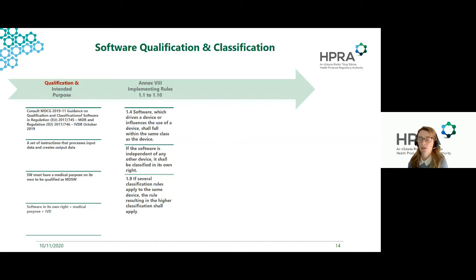Then, according to the second indent of rule 1.4, if the software is independent of any other device, it shall be classified in its own right. In determining the proper classification of medical device software under the IVDR, the manufacturer shall consider all classification and implementing rules of the IVDR. And again, as spelled out by implementing rule 1.1 of Annex 8 of the IVDR, the application of the classification rules shall be governed by the intended purpose of the medical device software.